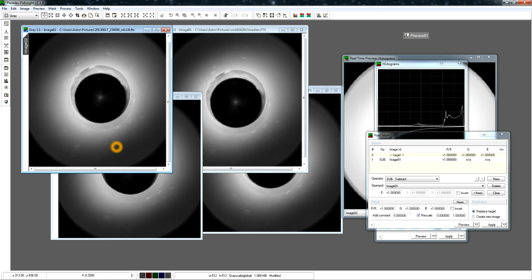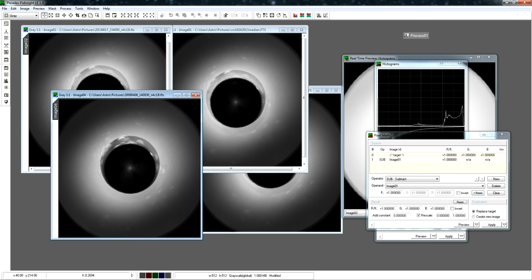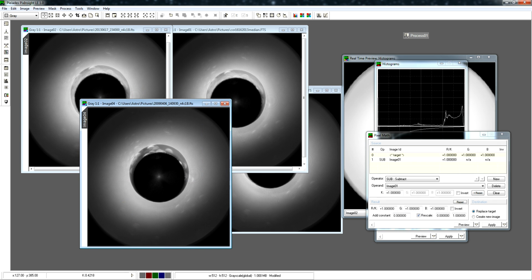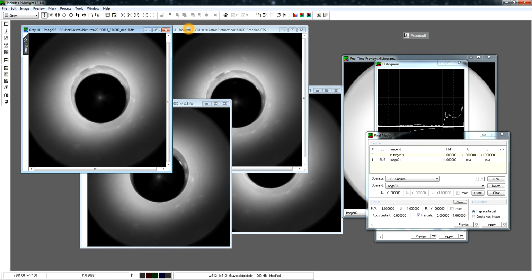Now in this case, it appears that there's no new dust motes. The number of dust motes appears to be stable. Even if you look back on 2009, you can see the offending dust mote right here, but it has moved a little bit, just enough to throw off the calibration frame.